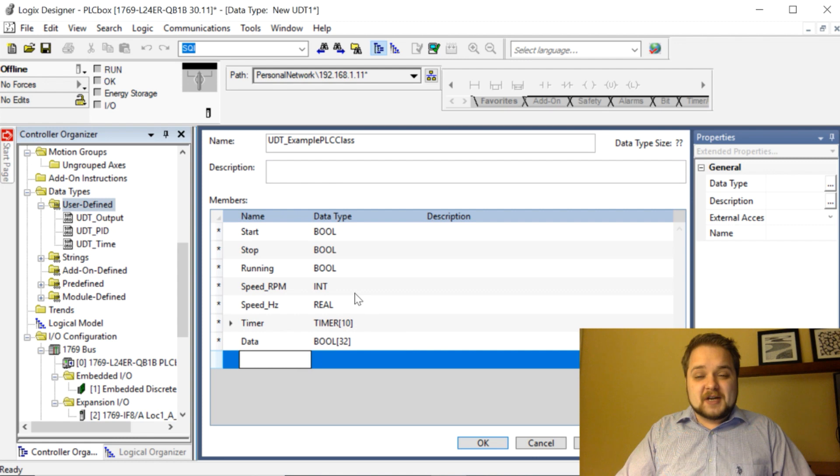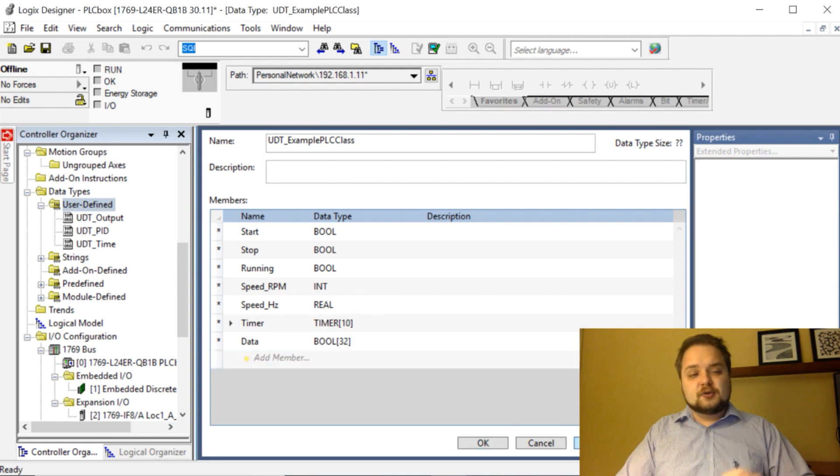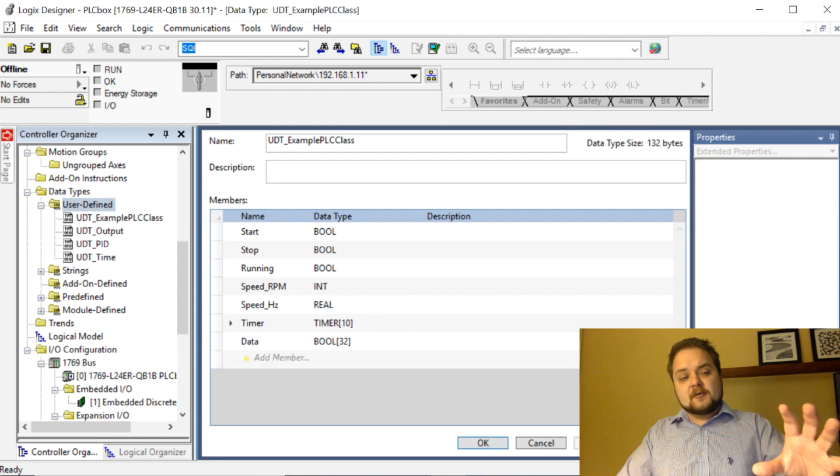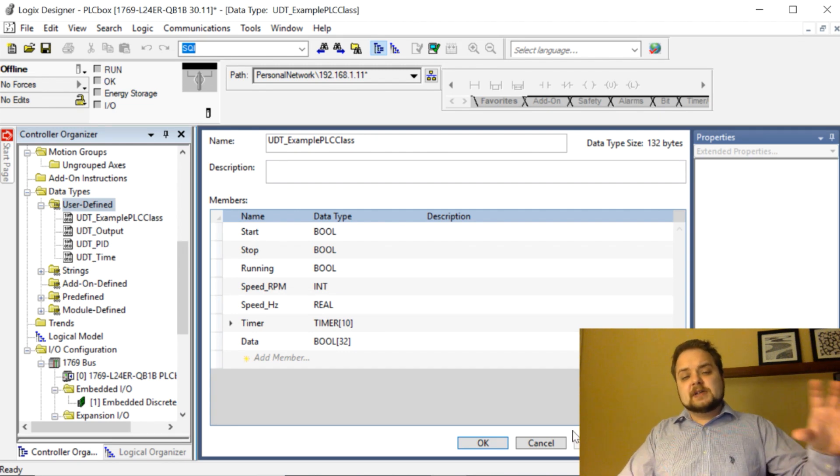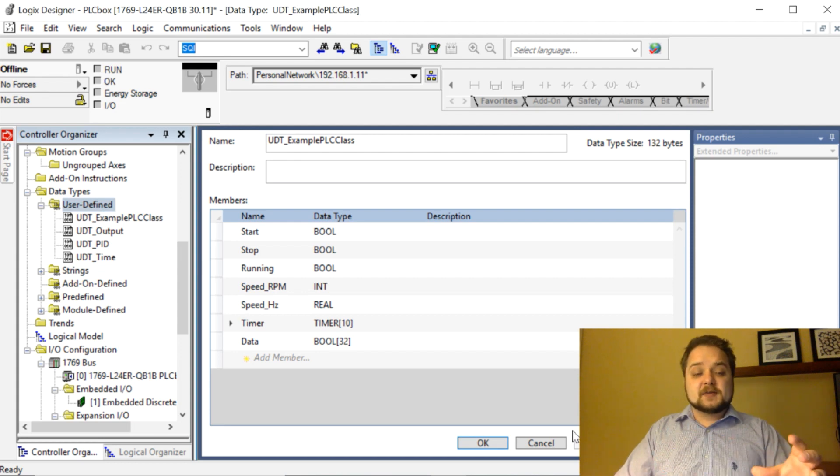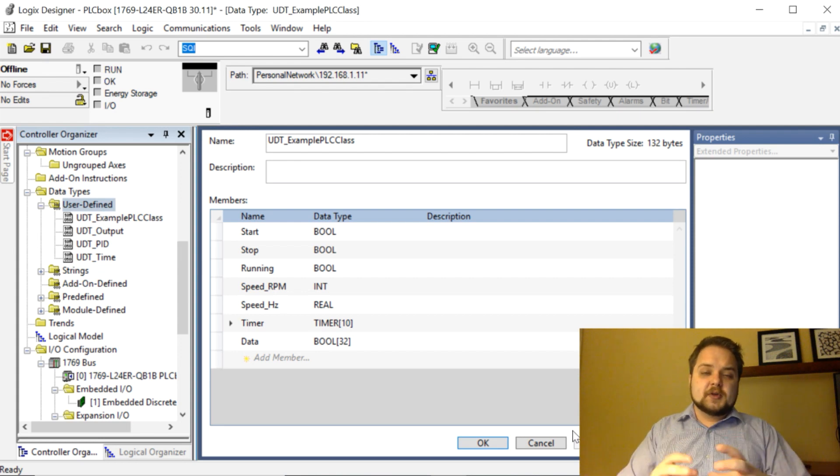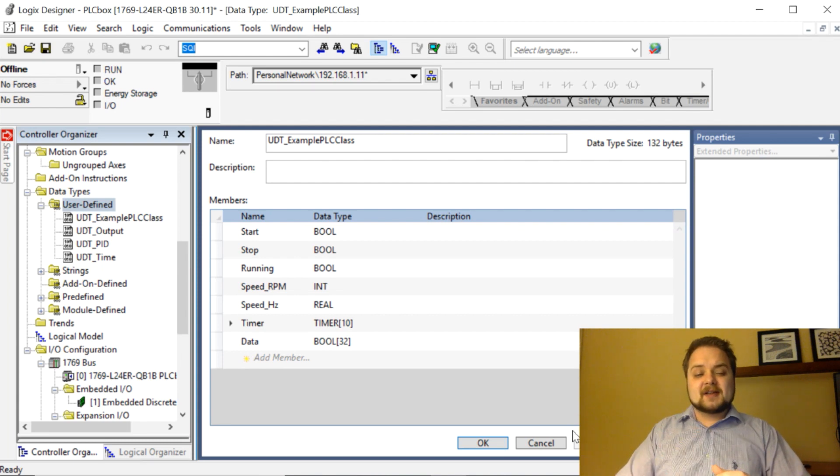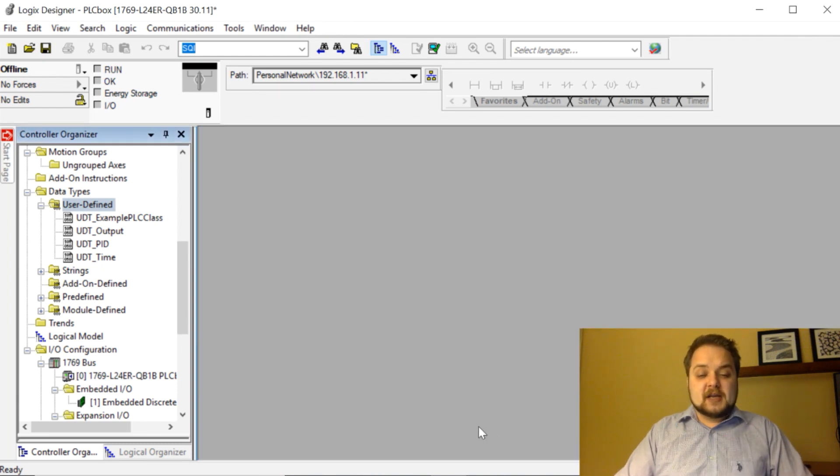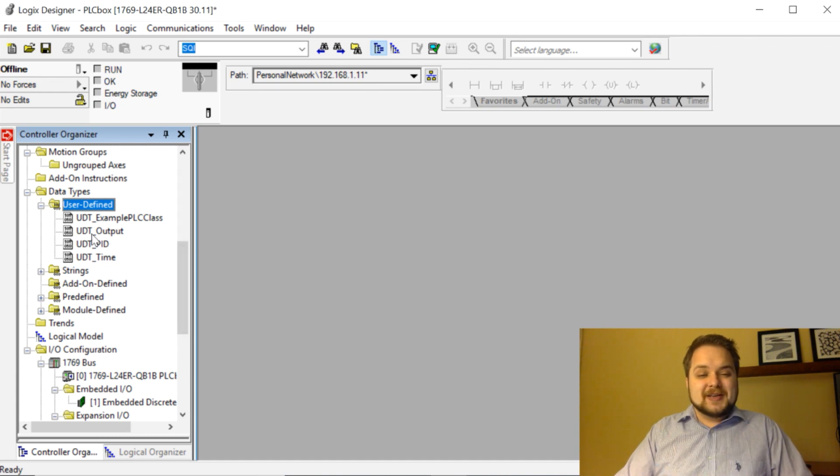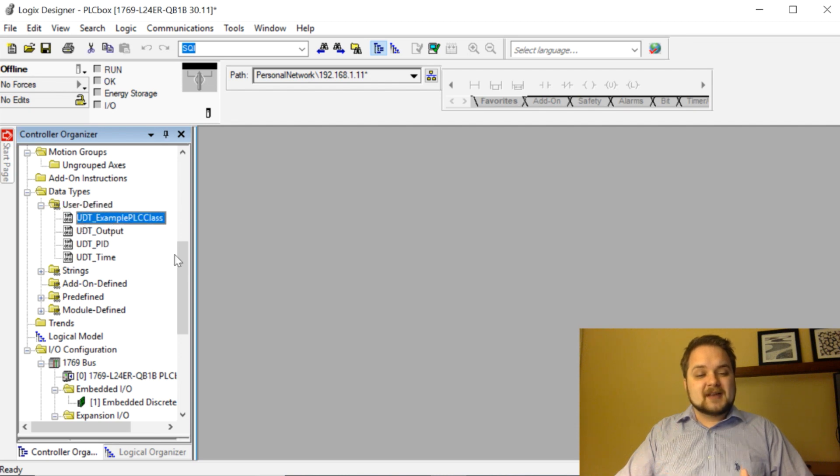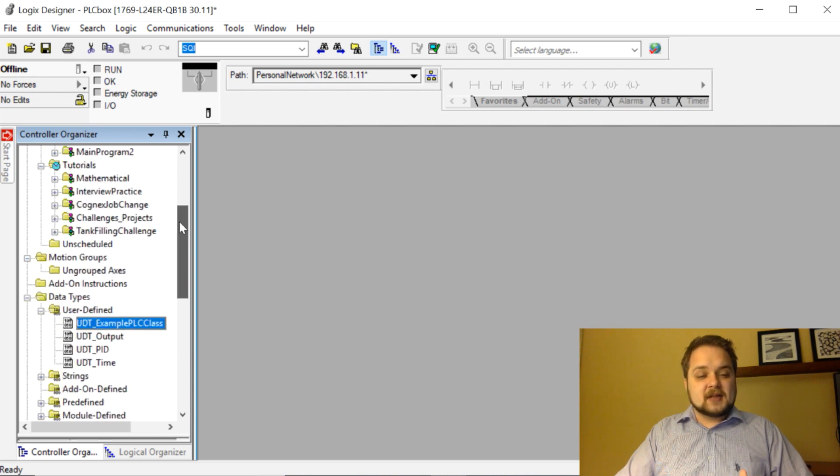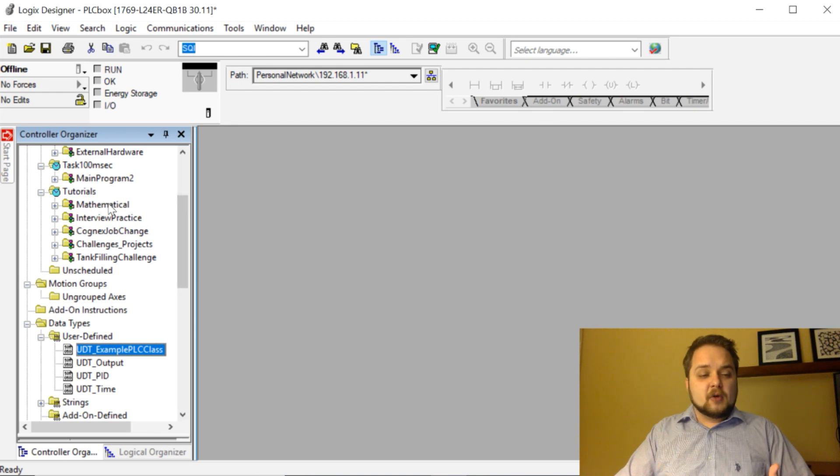Once you're done editing your UDT you can hit apply, and do notice that I'm obviously working with this on an offline file because once UDTs are sent to a controller you cannot simply modify them live. Usually what you can do is you can export and import and override a certain UDT but it's not as easy to change them once they are on a live controller. Once we commit to that particular UDT, as you can see it is going to be listed right here. UDT example PLC class and now it becomes usable all over the program.